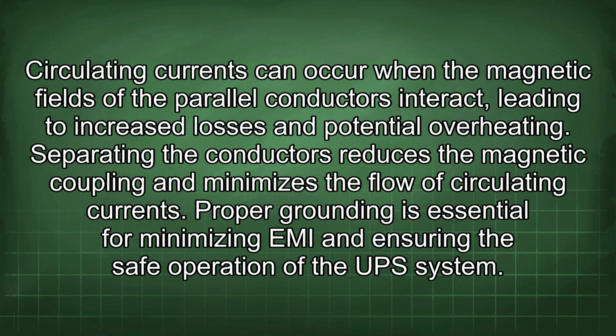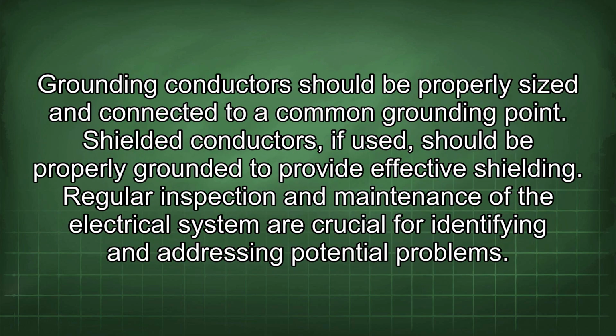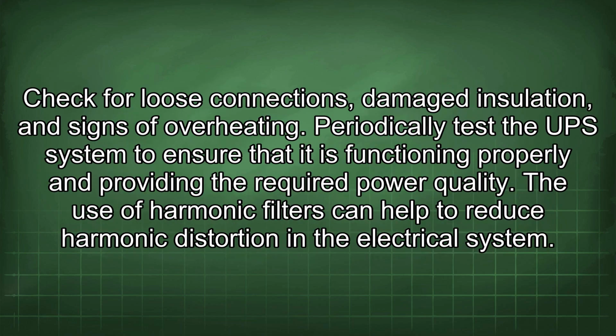Proper grounding is essential for minimizing EMI and ensuring the safe operation of the UPS system. Grounding conductors should be properly sized and connected to a common grounding point. Shielded conductors, if used, should be properly grounded to provide effective shielding. Regular inspection and maintenance of the electrical system are crucial for identifying and addressing potential problems. Check for loose connections, damaged insulation, and signs of overheating. Periodically test the UPS system to ensure that it is functioning properly and providing the required power quality.